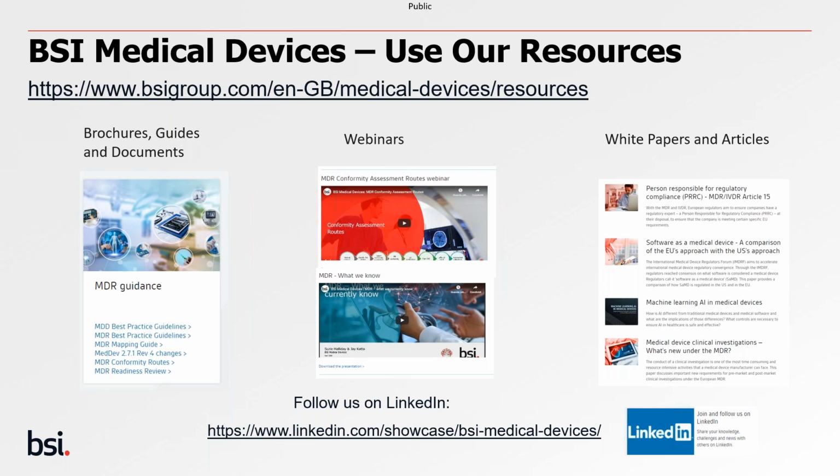And also you need to confirm whether your device is still state of the art. So you need to think about what that timeline looks like and justify that timeline. Article 61(10) devices are class 2a, 2b non-implantable devices, so therefore there could be class 1. They are lower risk, so it could be justified to consider a longer timeline to conduct those literature searches. Okay, brilliant, thank you.